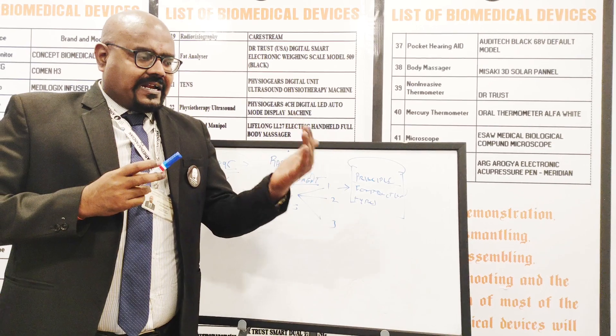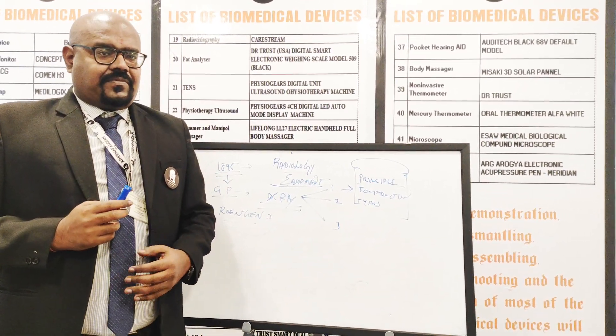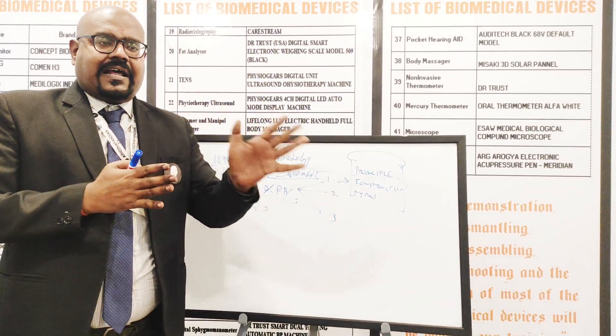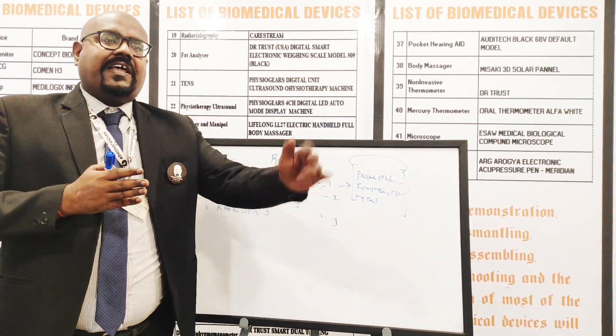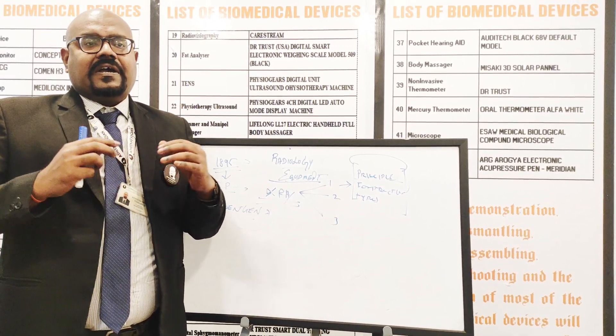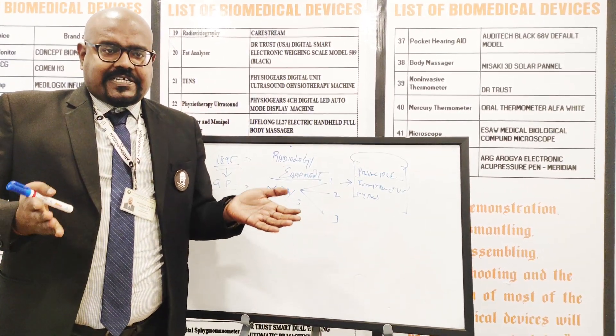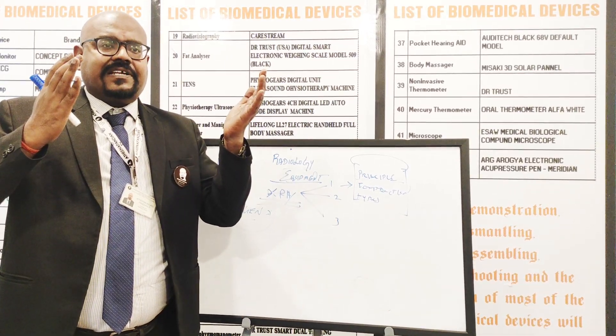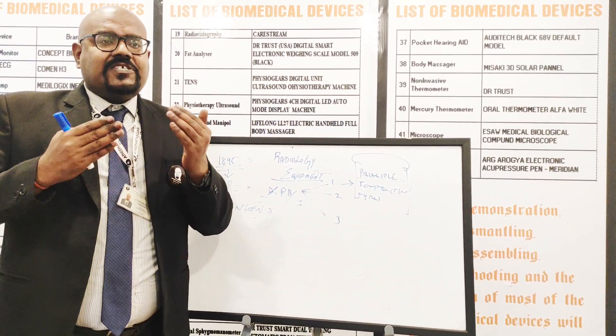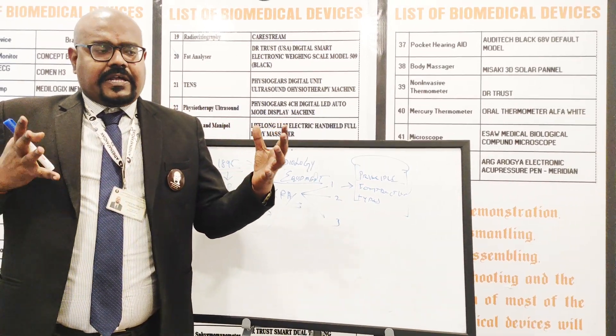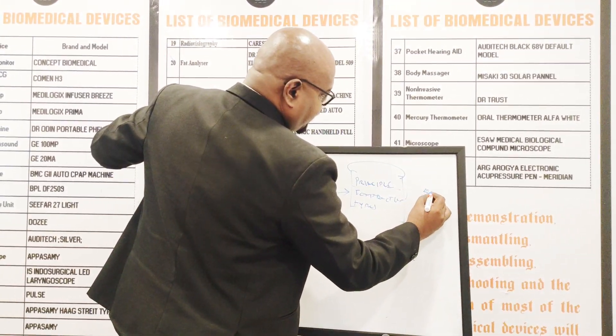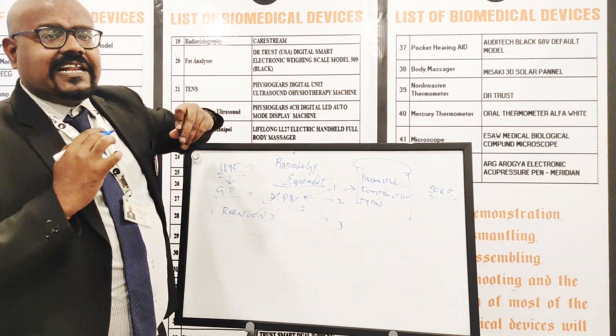X-rays are generated using electrons. We are all well aware that the flow of electrons is essentially current. By increasing the speed of electrons, we can generate X-rays. The first way to increase electron speed is by increasing the potential difference. As potential difference increases, the velocity of electrons increases. We can apply up to 50 kV for the generation of X-rays.